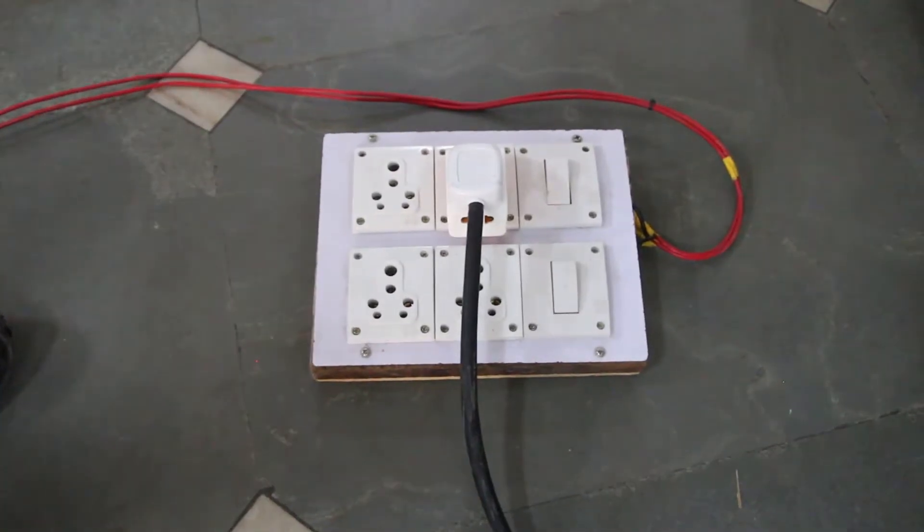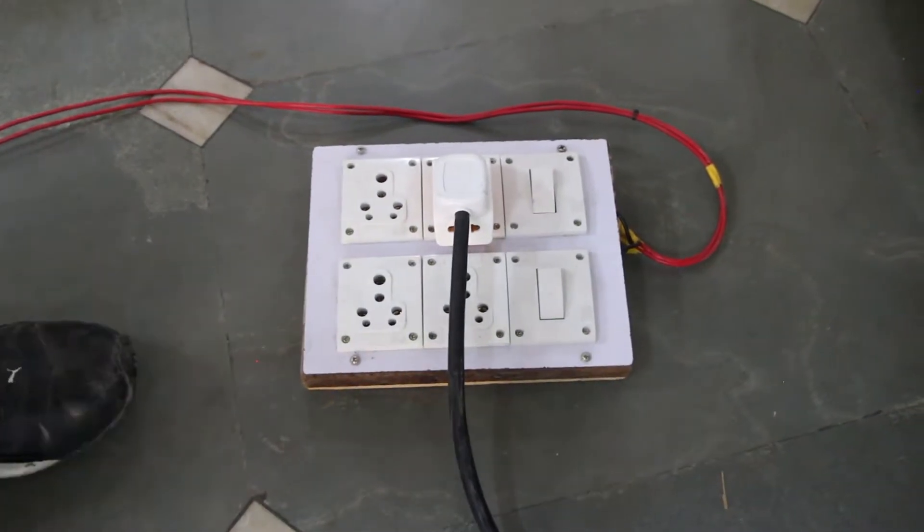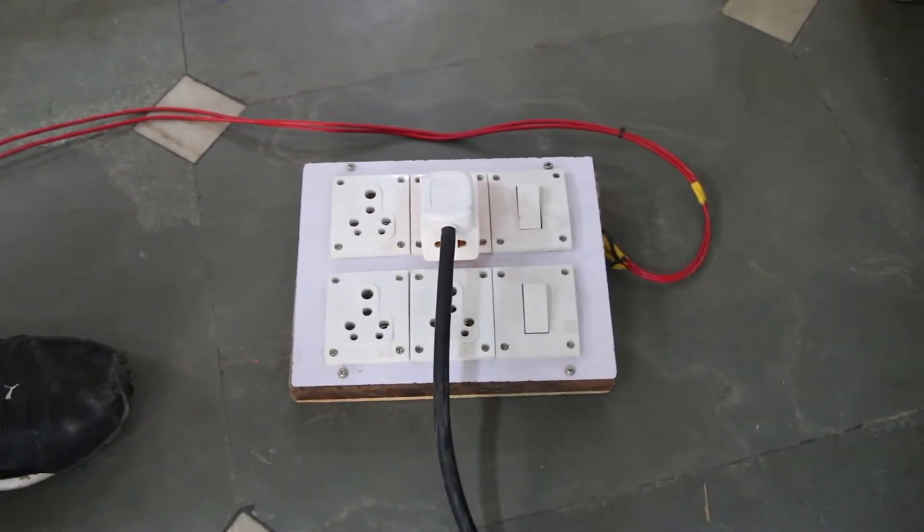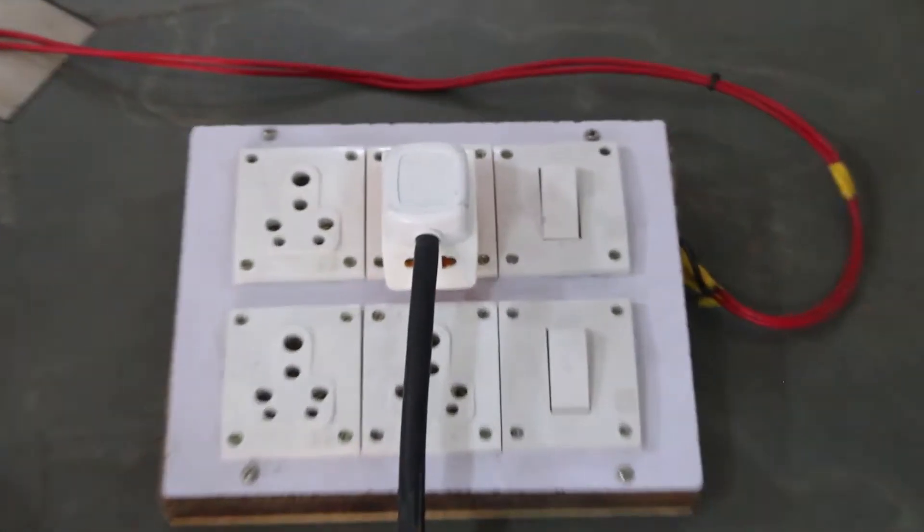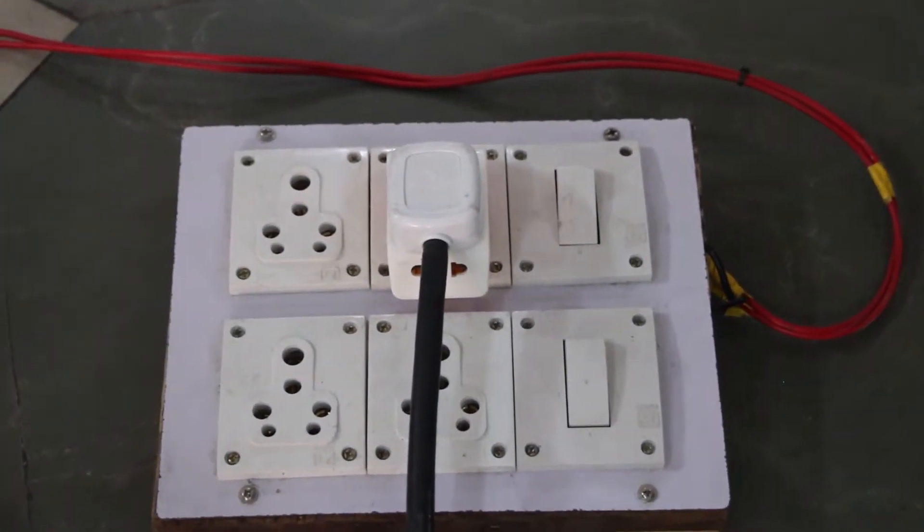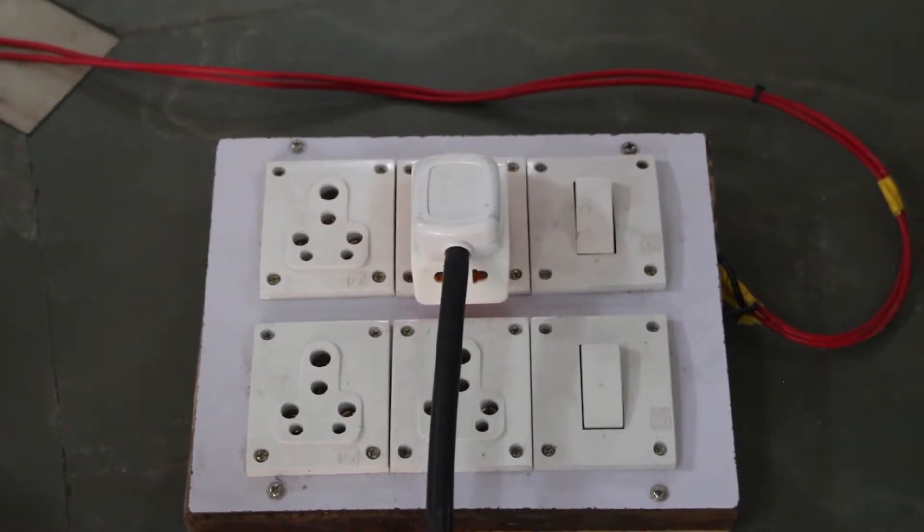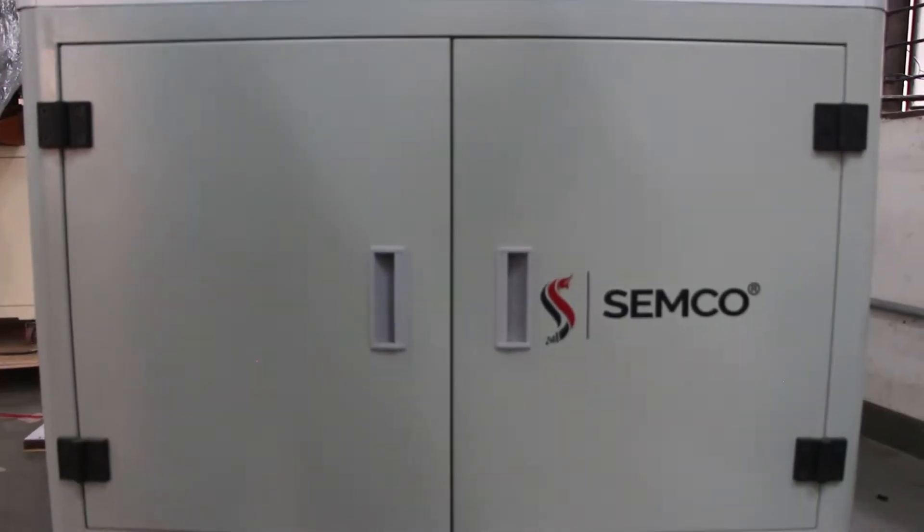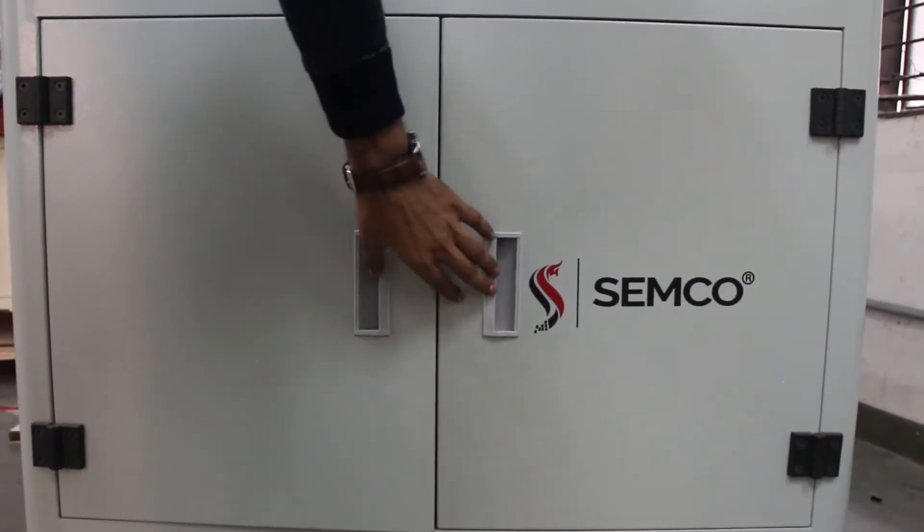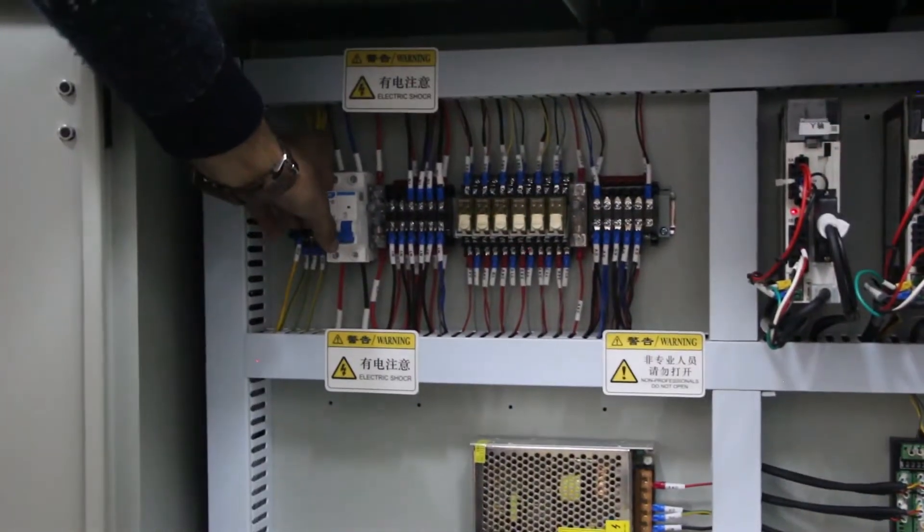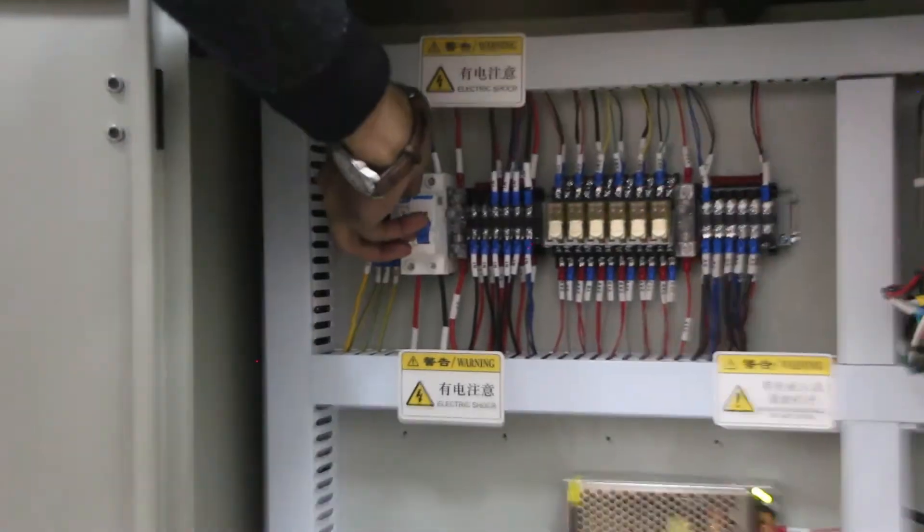Double-sided automatic welding machine needs single phase connection. As you can see, there is a single phase connection we have connected already. But current needs more than 20 amps AC. So we care about your MCB limitation should be more than 20 amperes. Now there is an additional power circuit breaker there. You can see there. This is an MCB. We have to operate from there also.